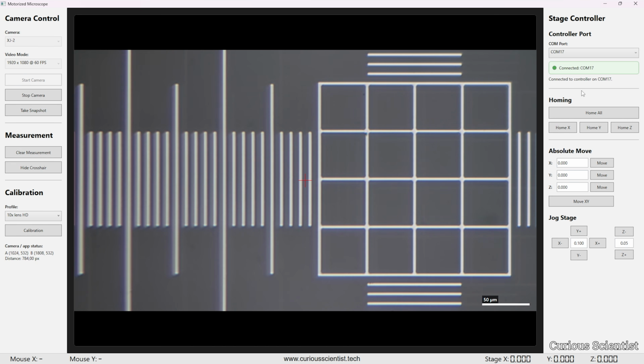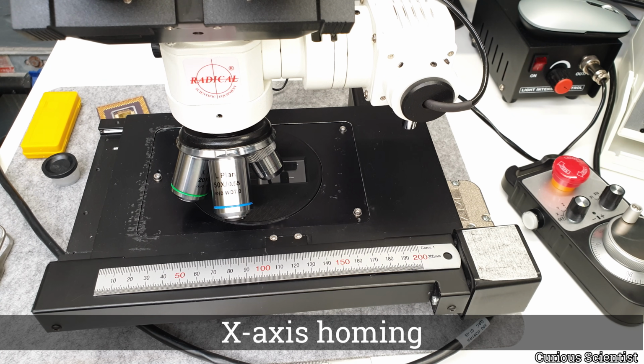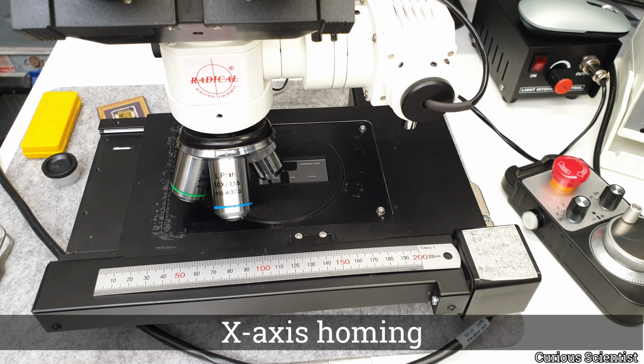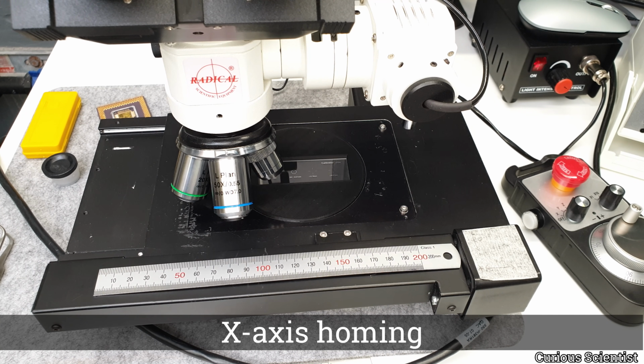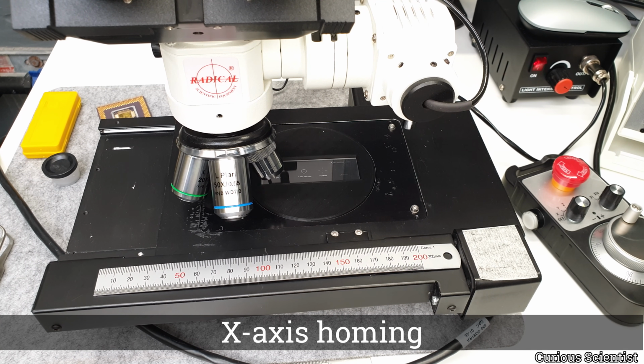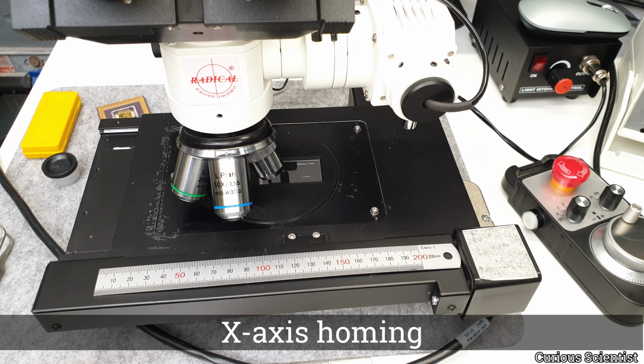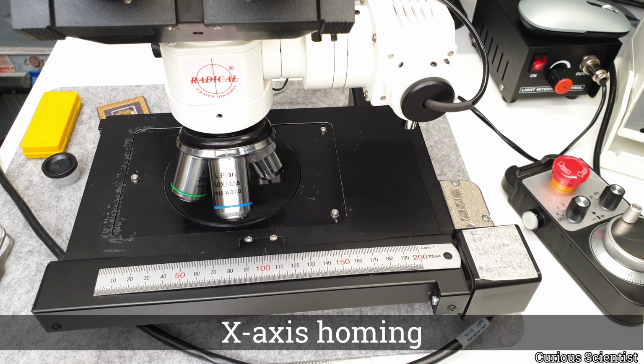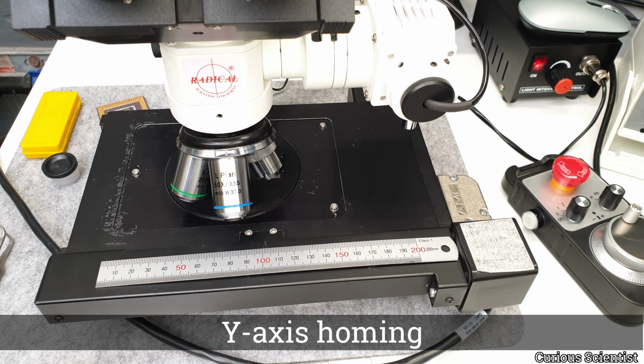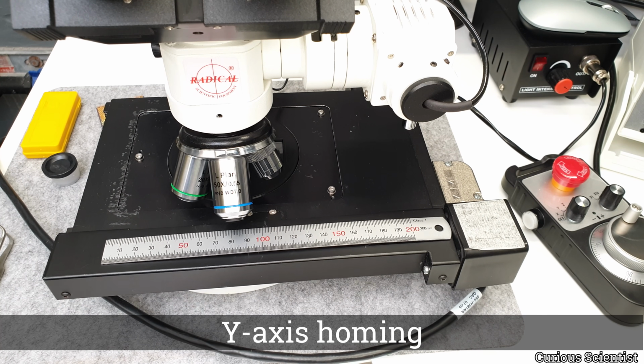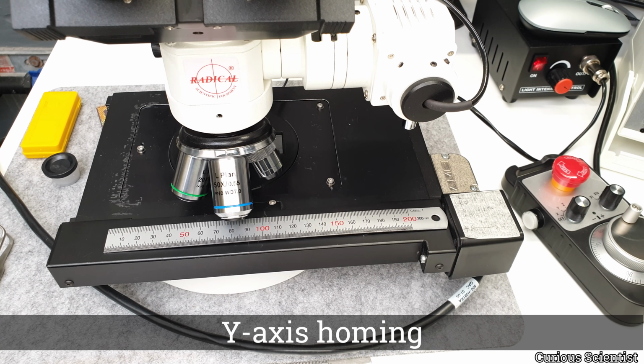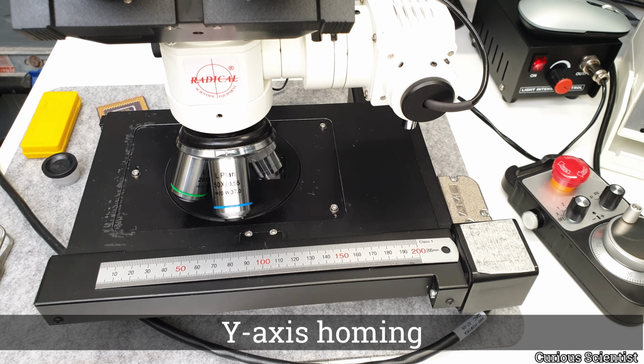This can be done at once by clicking the Home All button, or one by one by clicking the corresponding button for each axis. The homing of the stage, X and Y axis, is straightforward. In both cases, the stage is driven until the limit switch on the motor side is hit. Then, the motor is driven until the switch is released. This point becomes the 0 coordinate of the axis. Then, the axis is driven until the physical center of the axis is reached.